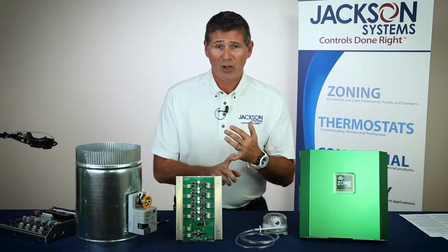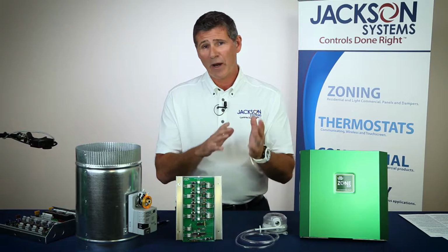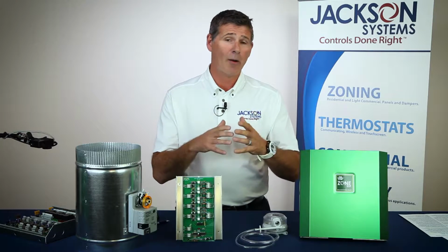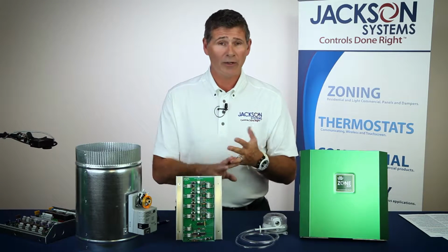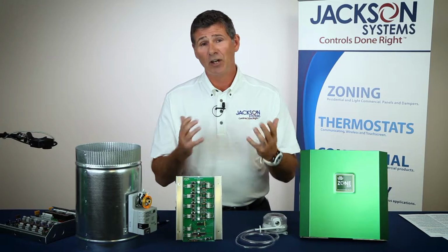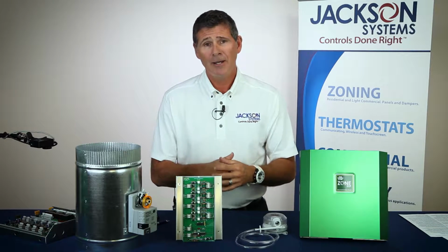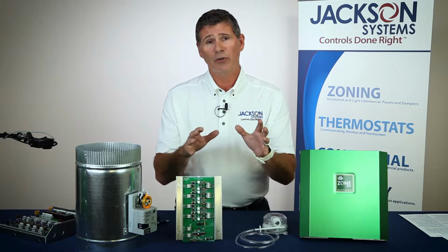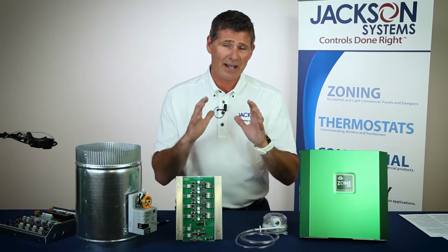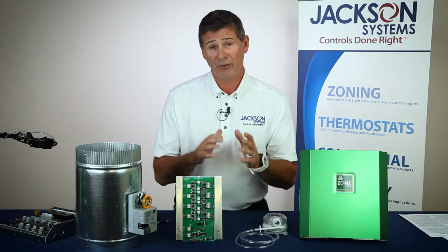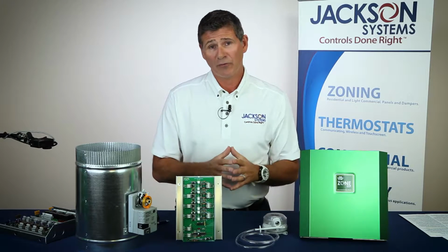No more having to install a bypass damper, trying to figure out the weights, where to adjust it so that it accommodates the pressure when needed. No more added expense or hassle of adding ductwork into tight or cramped spaces. Installing this system with our zone control system is going to eliminate the need to ever install a bypass system ever again. So we sell it in one of two ways.